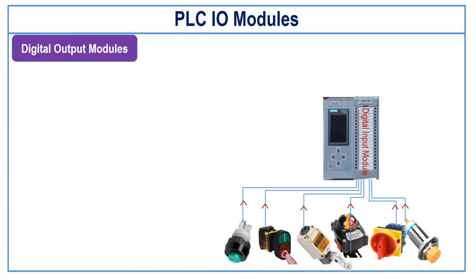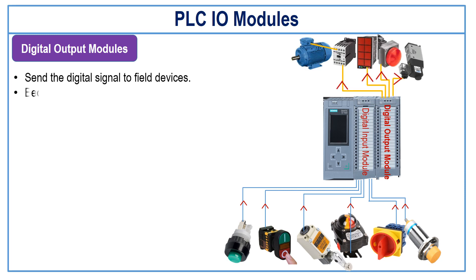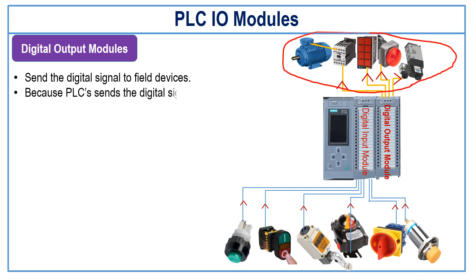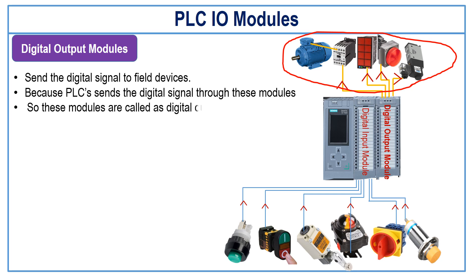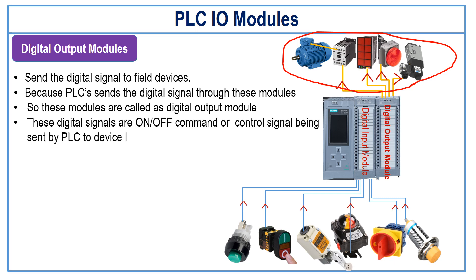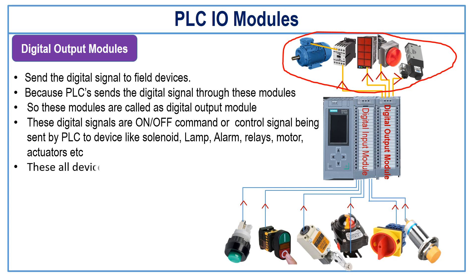Digital output modules: The digital output modules send the digital signal to the field devices. Since the PLC sends the digital signal through these modules, they are called digital output modules. These digital signals are basically on or off commands or control signals being sent by the PLC to devices like solenoid, lamp, alarm, relay, motors, and actuators. These all devices can be connected to the digital output modules.